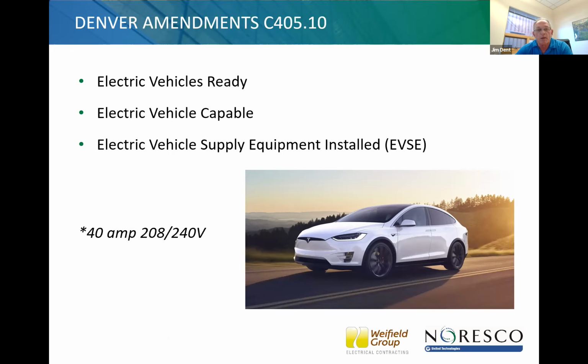They've got three definitions. Electric vehicles ready is there's a 2-pole 40 amp circuit pulled to a parking space from a panel that's energized, ready to go. Electric vehicle capable is having an empty conduit from an electrical room to every parking space. Well, depending on commercial or residential. In residential in Denver, you've got to have a conduit to every parking space. In an office building, it's like 10%. And then 5% of the spaces have to have electric vehicle supply equipment installed, which means there actually has to be charging equipment installed. So you have to be knowledgeable about what the definition is, because the definition of electric vehicles ready in Boulder is different than electric vehicles ready in Denver. And that's something we'll address here in just a few minutes.